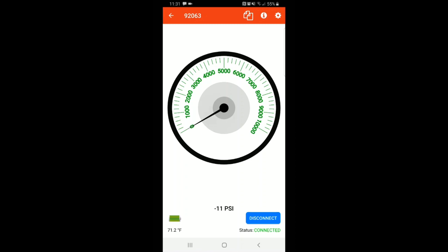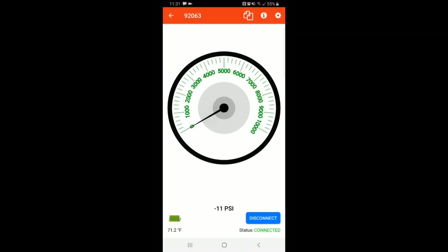In order to zero the gauge before you use it on the machine, you simply click on the display where it says negative 11 psi, and it will prompt you to zero the pressure. By simply selecting yes, you now see that it will zero. Additionally, through this screen, you have the ability to disconnect from the sensor, which is shown in the bottom right-hand corner. Displayed in the bottom left-hand corner will be battery life, as well as ambient air temperature.